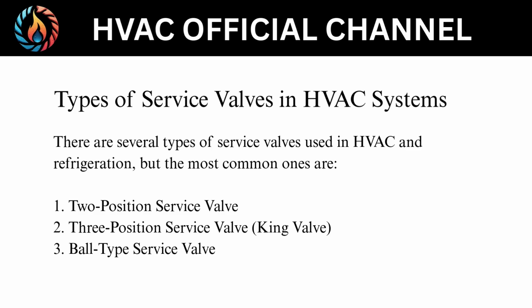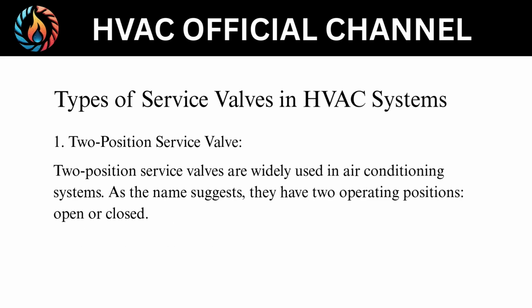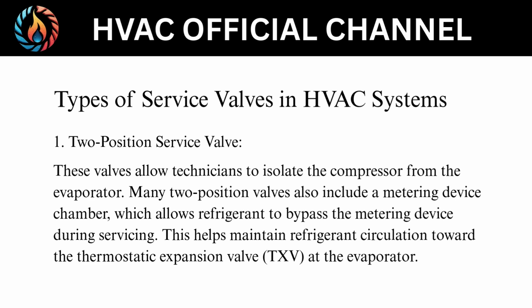Types of service valves in HVAC systems. There are several types of service valves used in HVAC and refrigeration, but the most common ones are: 1. Two-position service valve. Two-position service valves are widely used in air conditioning systems. As the name suggests, they have two operating positions, open or closed. These valves allow technicians to isolate the compressor from the evaporator. Many two-position valves also include a metering device chamber, which allows refrigerant to bypass the metering device during servicing. This helps maintain refrigerant circulation toward the thermostatic expansion valve, TXV, at the evaporator.